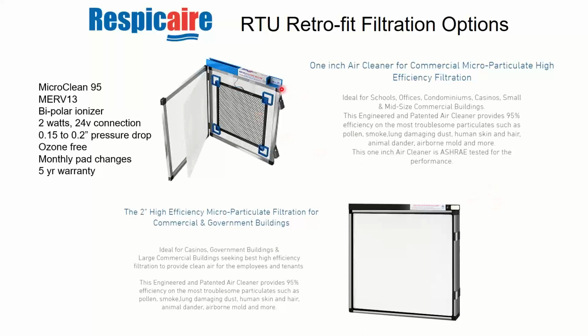They have 24-volt power that comes to them. 24 volts is low voltage, so I typically don't have to put it in conduit for most codes. And I have 24 volts readily available in most rooftop units. By most, I mean all. So it makes it pretty easy to set this up.